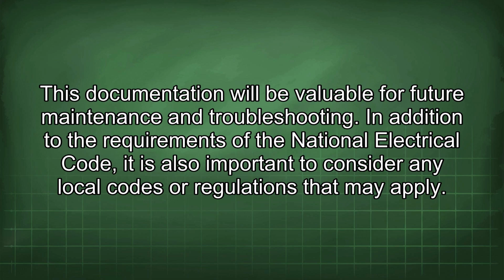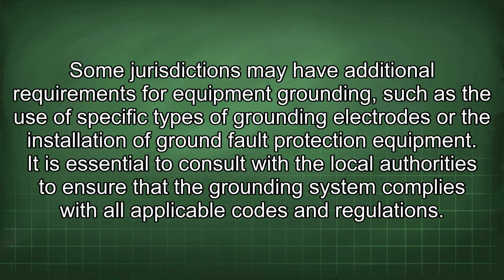In addition to the requirements of the National Electrical Code, it is also important to consider any local codes or regulations that may apply. Some jurisdictions may have additional requirements for equipment grounding, such as the use of specific types of grounding electrodes or the installation of ground fault protection equipment. It is essential to consult with the local authorities to ensure that the grounding system complies with all applicable codes and regulations.